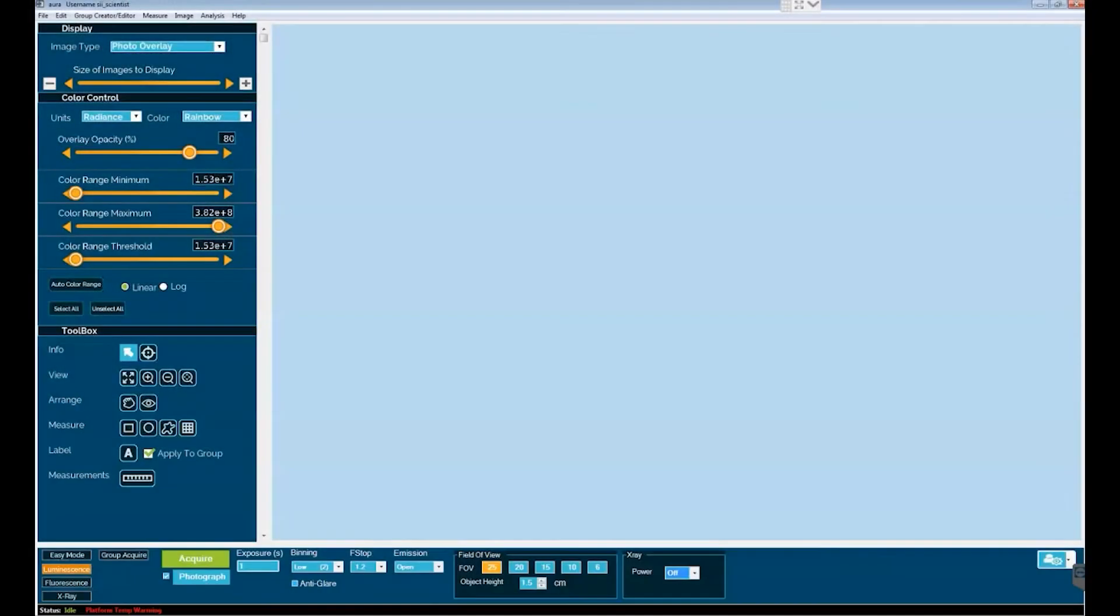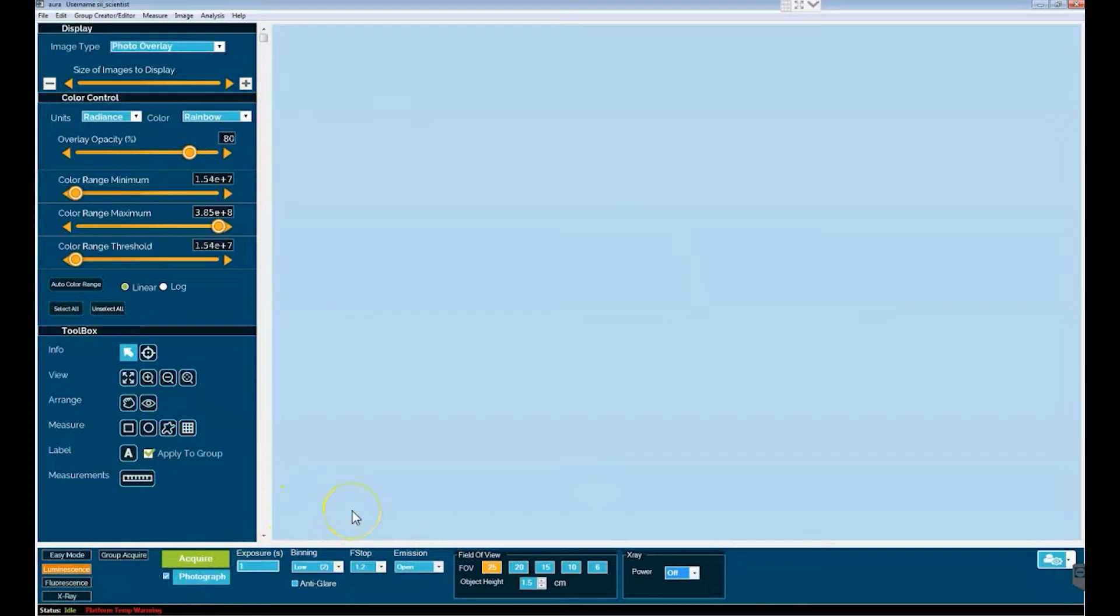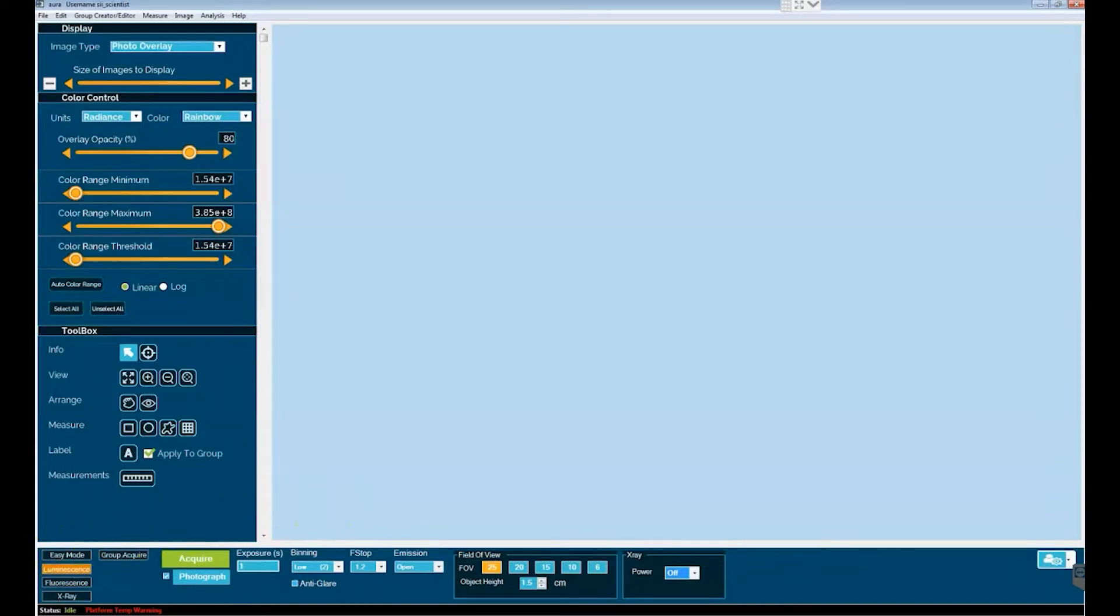Now in this tutorial we are going to demonstrate how to do a standard luminescent acquisition here on the home page of Aura 4.0 making use of an AMY HTX imaging system. You would go down to the bottom left hand corner and you will see that there are four tabs indicating the type of imaging that one can do.